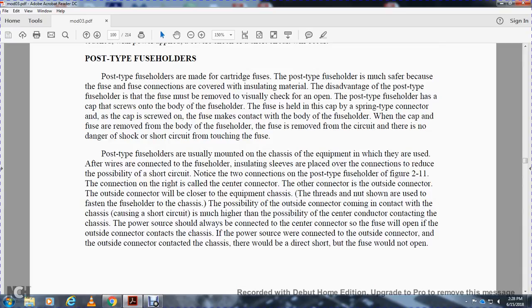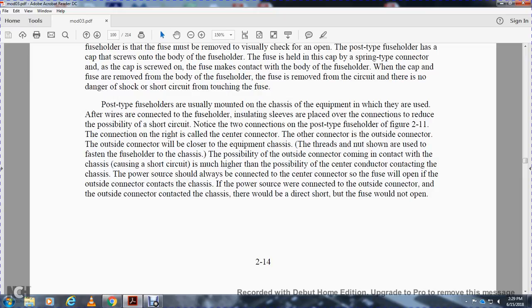The post type fuse holder is made for cartridge fuses. The post type fuse holder is much safer because the fuse connections are covered with insulating material. However, the fuse must be removed to visually check if it is open. The post type fuse holder has a cap that screws onto the body of the fuse holder - there is no danger of shock or short circuit from touching the fuse. The post type fuse holder is usually mounted on the chassis of the equipment. After the wire is connected to the fuse holder, an insulating sleeve or plate covers the connection to prevent the possibility of a short circuit. Note that the two connections on the post type fuse holder - as shown in Figure 2-11 - the connection on the right is called the center connector, and the other connection on the outside is called the outside connector. The outside connector is close to the equipment chassis. Threads and nuts are not shown, but the fuse holder is mounted to the chassis. Care should be taken that the outside connector does not contact the chassis, as this would cause a short circuit.